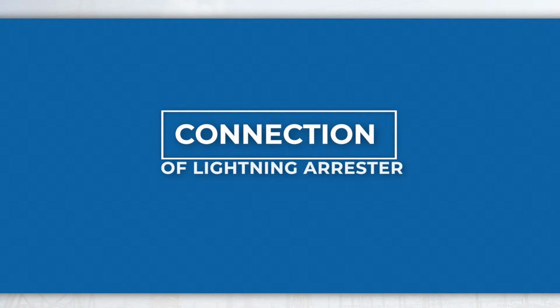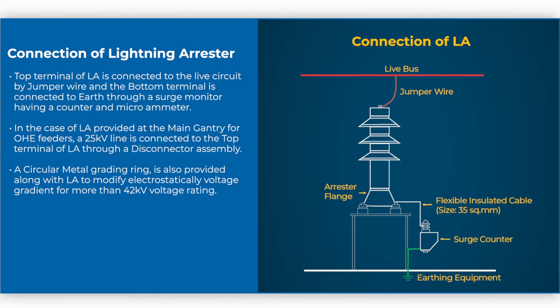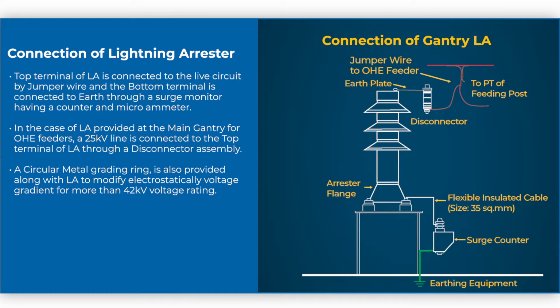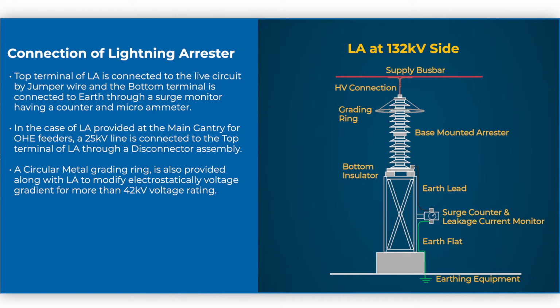Connection of lightning arrestor. The top terminal of LA is connected to the live circuit by jumper wire and the bottom terminal is connected to earth through a surge monitor having a counter and micro ammeter. In the case of LA provided at the main gantry for OHE feeders, a 25 kV line is connected to the top terminal of LA through a disconnector assembly. A circular metal grading ring is also provided along with LA to modify electrostatically the voltage gradient for more than 42 kV voltage rating.